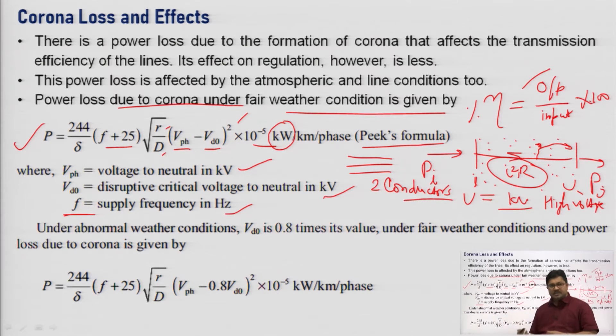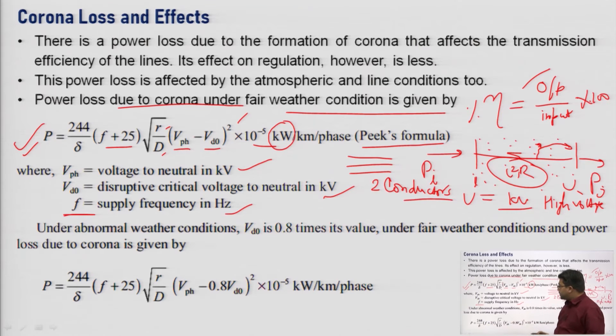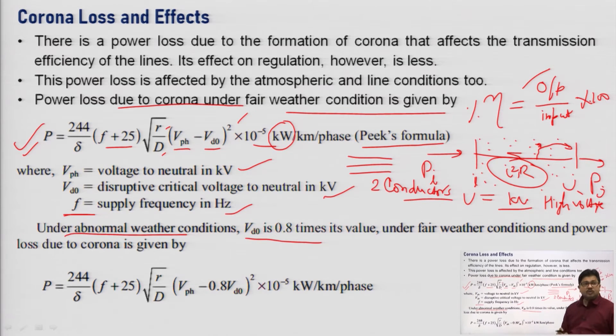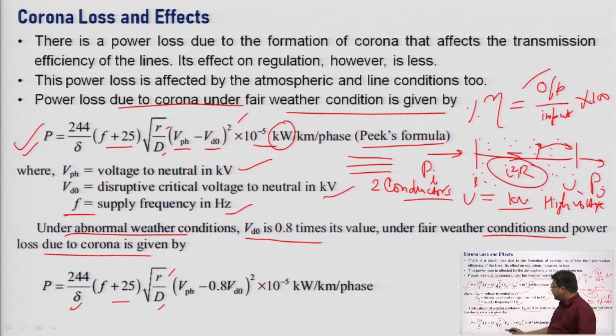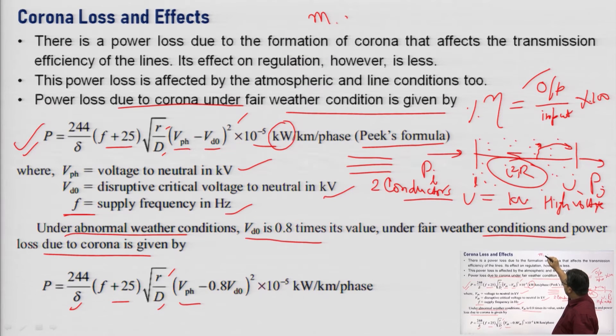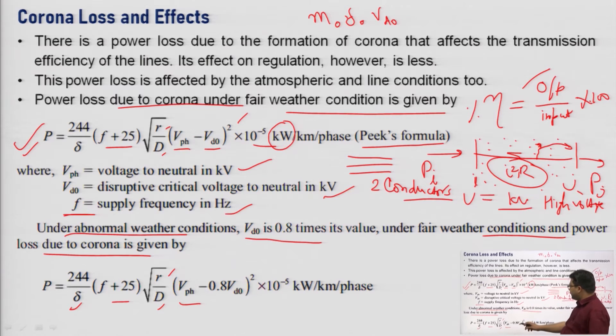Under abnormal weather conditions, this formula changes. The normal weather condition formula applies for normal temperature, pressure, and fair environment. Under abnormal weather, V_d0 is taken as 0.8 times its fair weather value. The power loss due to corona under abnormal weather is: P = (244/δ) × (f + 25) × √(r/D) × (V_ph − 0.8·m₀·V_d0)² × 10⁻⁵ kilowatts per kilometer per phase, where m₀ is the conductor irregularity factor.